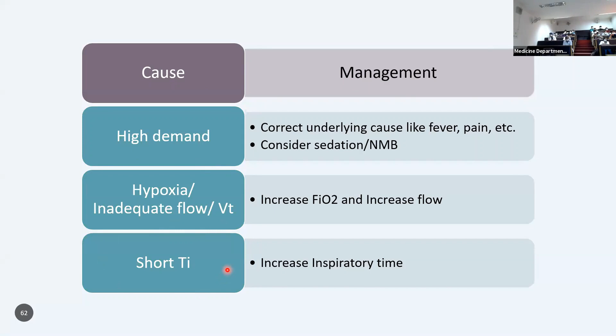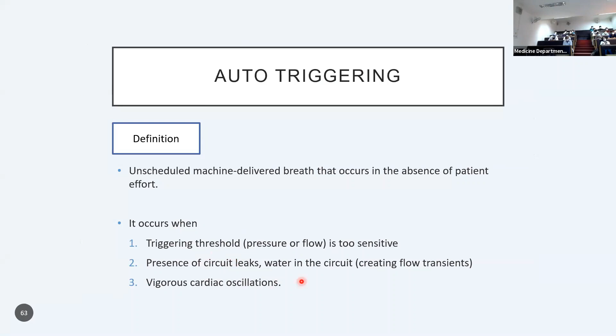Now coming on to auto-triggering. Auto-triggering is when triggering occurs due to non-respiratory stimuli, in absence of patient's effort. It may occur when the trigger threshold is too sensitive, that other minor perturbations in the circuit may induce a breath, or when there's circuit leak or water in the circuit, or when there's vigorous cardiac oscillations themselves inducing it.